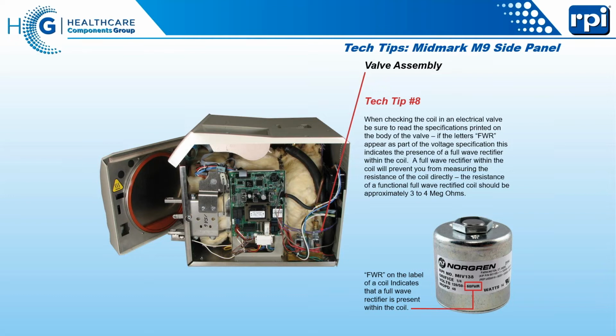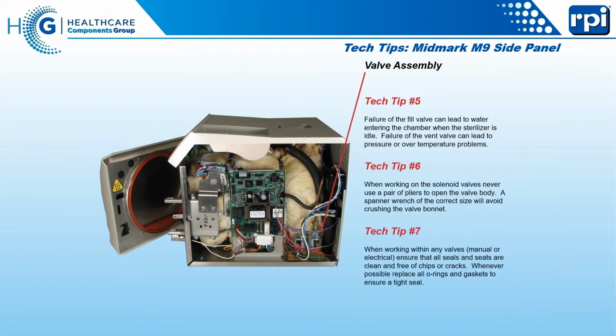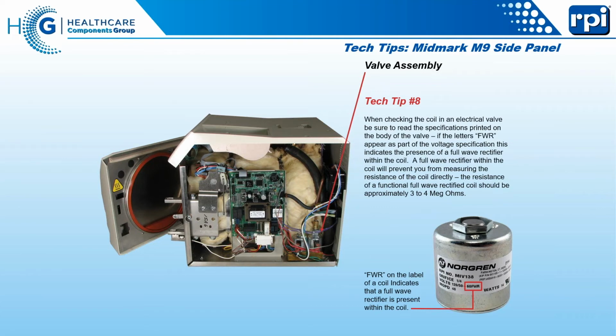Also in the Solenoid Solutions valves, they have a separate box that goes between the circuit board and the valve itself. That box has a full wave bridge rectifier in it. If you ever were to decide to go from a Solenoid Solutions valve to a Kip Norgren valve, you would take that block and you would throw it away. You can't put a full wave bridge rectifier on a full wave bridge rectifier. It will not work.